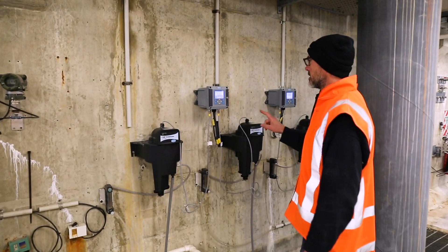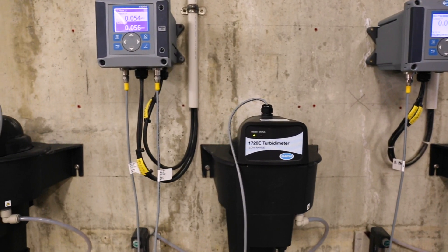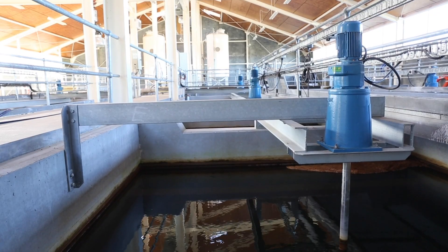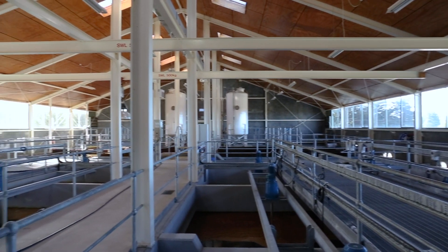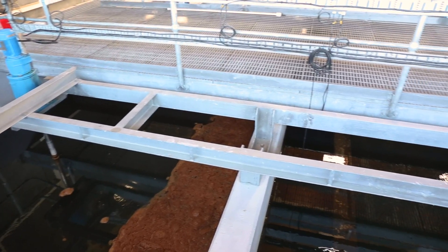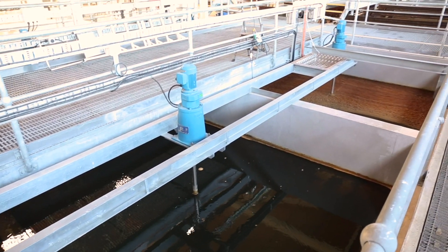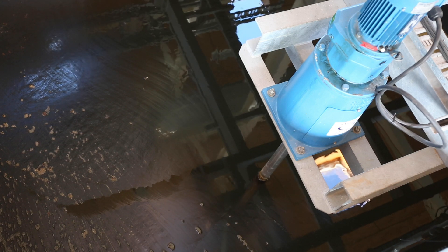The amount of foreign matter in the water, or turbidity, is carefully measured at several points in the process, so that improvements can be objectively monitored as the water continues its journey. The water is then split further into four streams, each of which passes through a series of three large floc tanks. Here the water is slowly stirred at a very specific rate, to allow the flocculation process to increase the size of the floc particles.